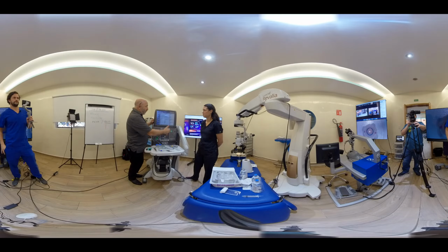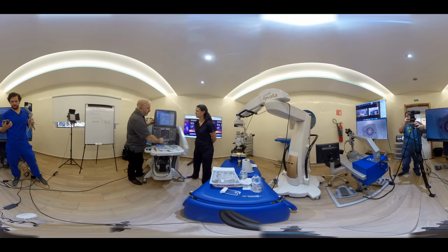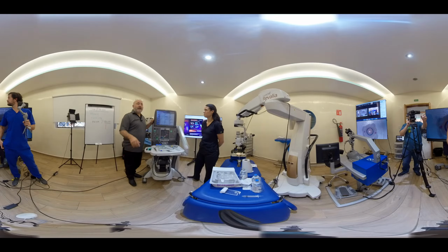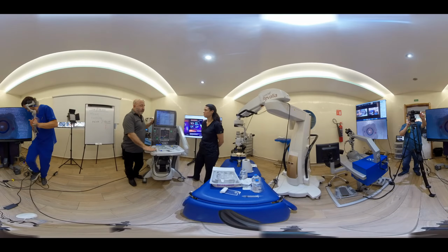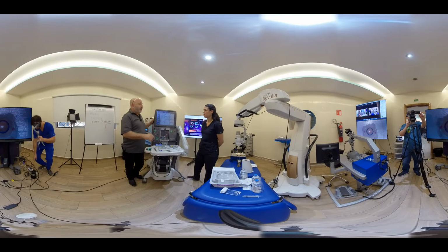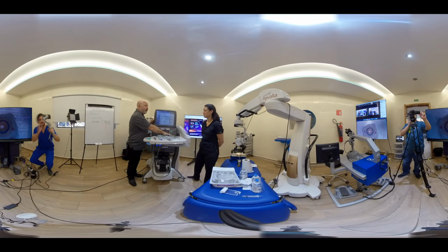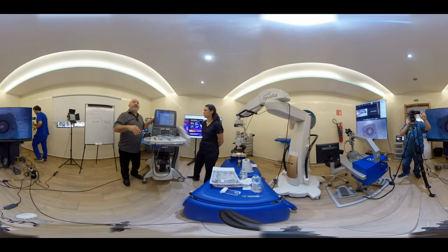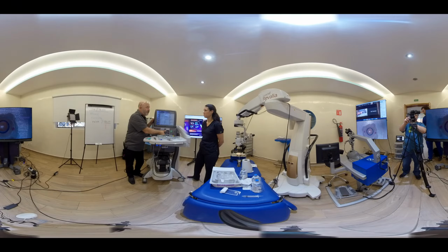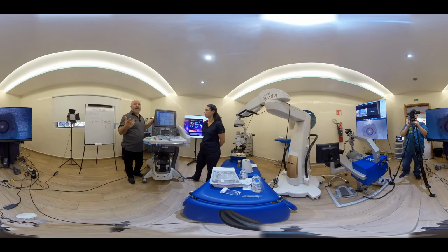So, the reason is, all the infusion comes in from the bottom of the cassette and upwards into all the chambers. And at the back here, at the connectors that go to the patient, there's a lot of turbulence as it's filling. If the tray is at this level or lower, the bubbles stay around that area. And then at some point, they just release and go into the infusion or the aspiration lines. But if I lift it up higher, and my preference is to be about the midpoint of the infusion chamber, or the bottom of the handle around here, then gravity can do its work, and those bubbles behind the cassette will float to the top of the cassette, and they won't come out when you least expect them.